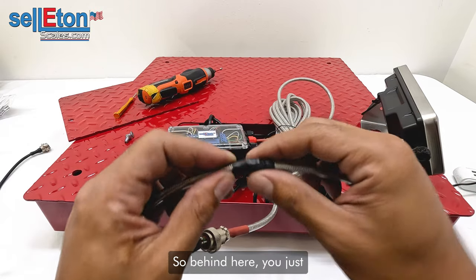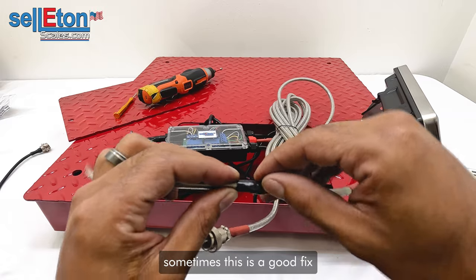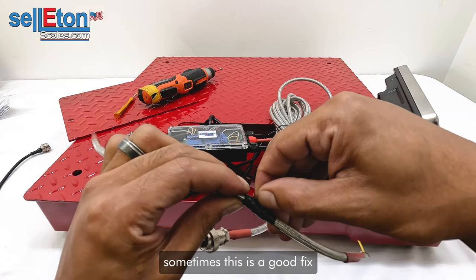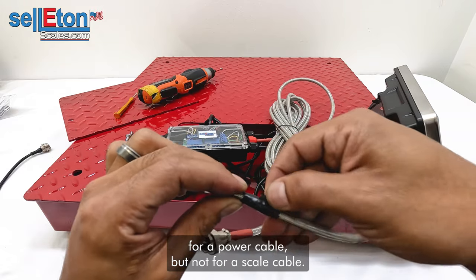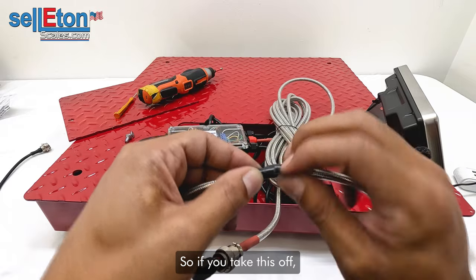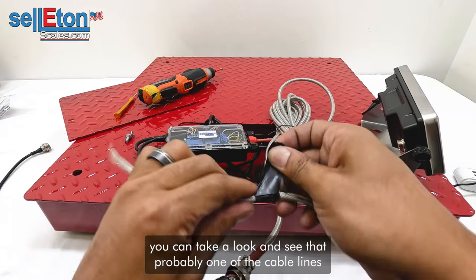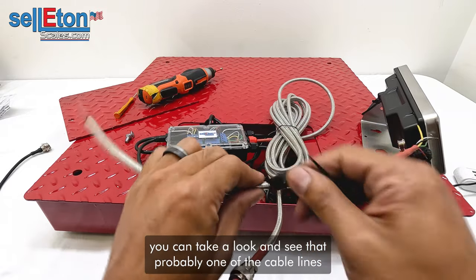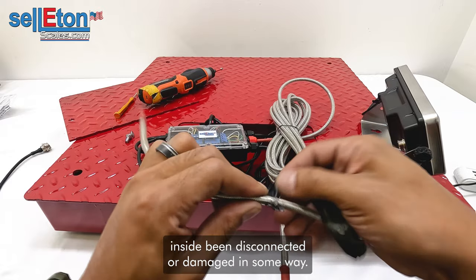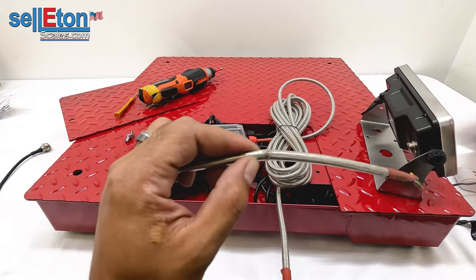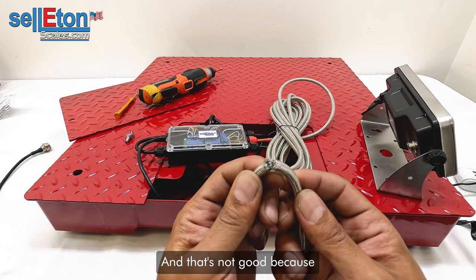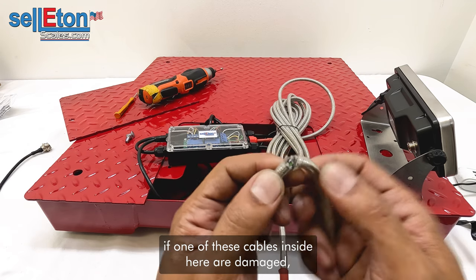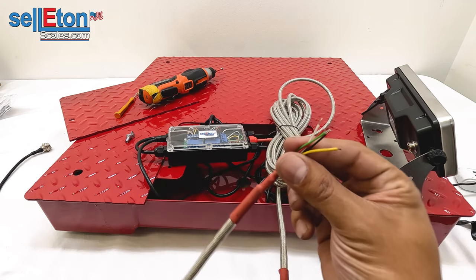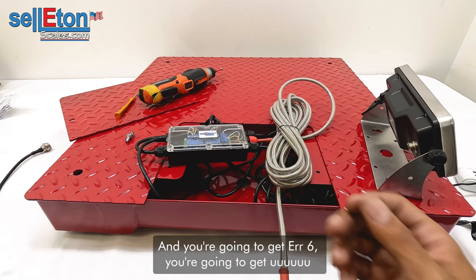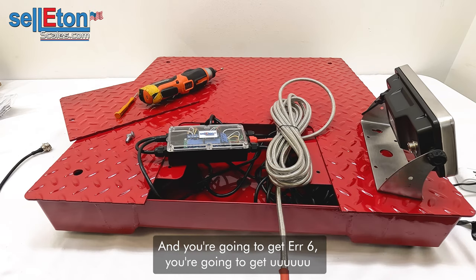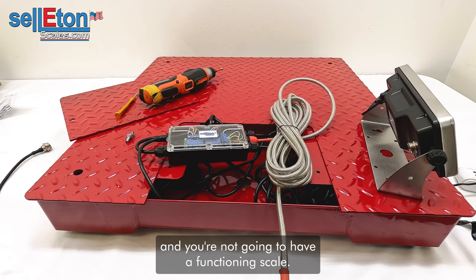Sometimes taping is a good fix for a power cable, but not for a scale cable. If you take this off, you can take a look and see that probably one of the cable lines inside has been disconnected or damaged in some way. That's not good, because if one of the cables inside of here is damaged, it's not going to work at all. You're going to get error 6, you're going to get USE, and you're not going to have a functioning scale.